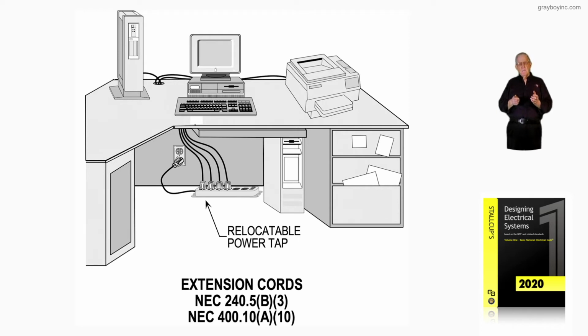So do you see, just by a quick count, how many things you might plug into a 20 amp circuit? And that's why the code says if it's a continued use, you're not to load the overcurrent device greater than 80%, because anything that you're using continuous, you have to multiply by 125%. But here we don't know during the day, everything you see there may be plugged in, some of it used continuous, some of it not. But it's a good rule of thumb.